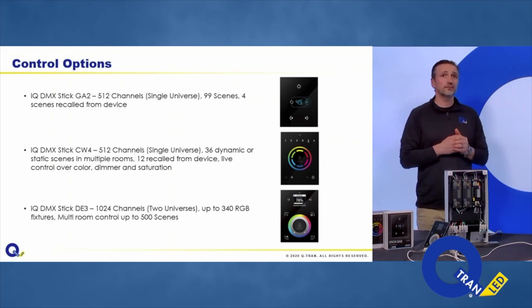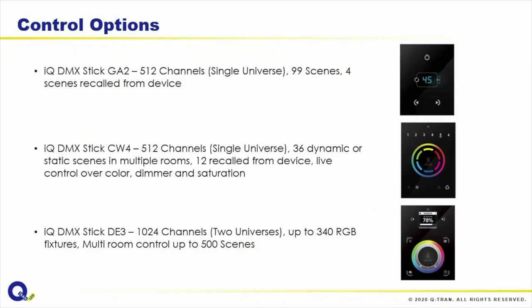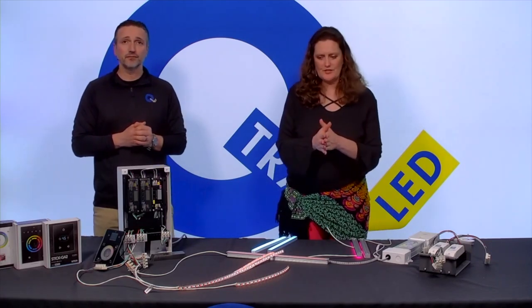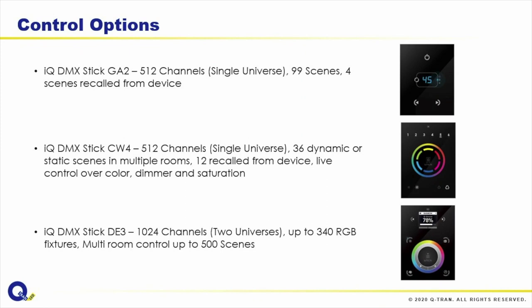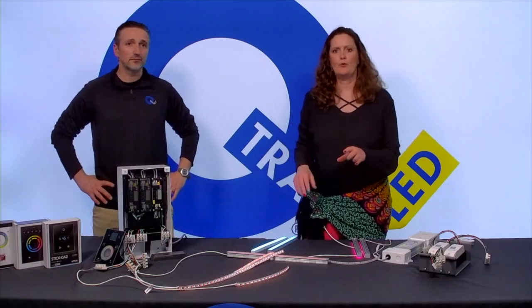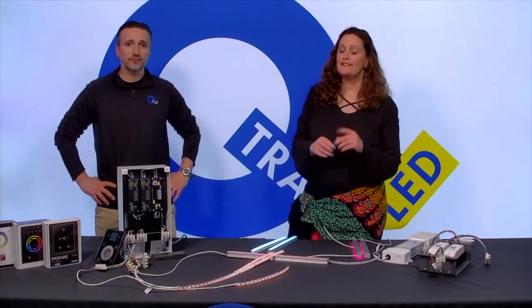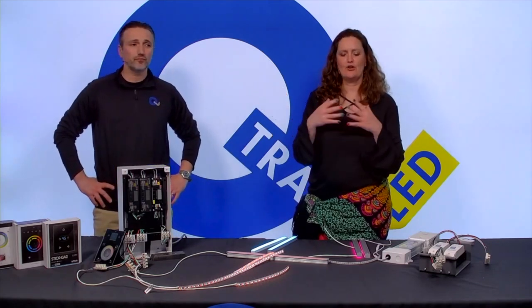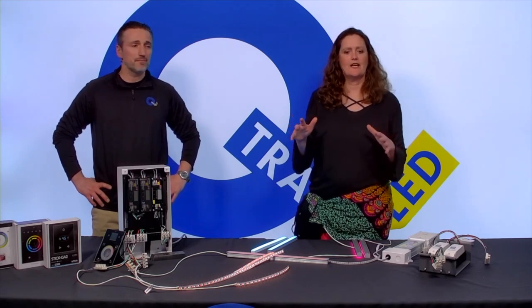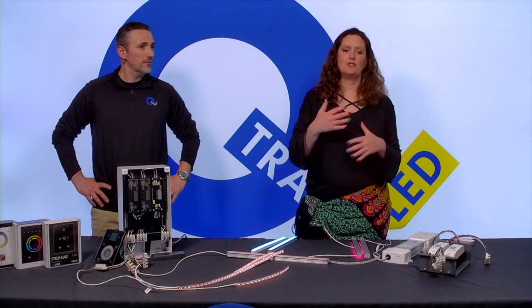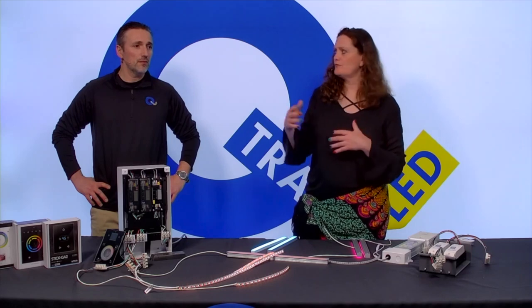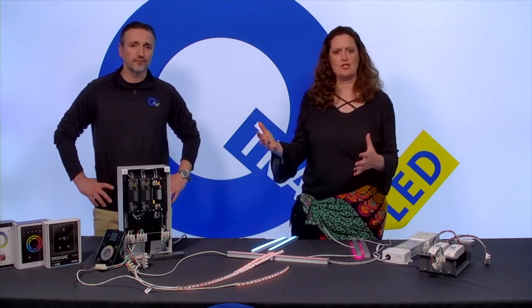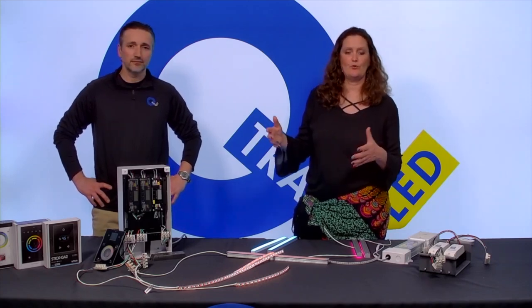To summarize the basic system: you have a DMX controller, a wire, and the system you're trying to operate. All three work together, with wiring being the most critical component. The DMX 512 wire between your control system and power supply is not a Q-Tran item — you must use DMX 512 standard wire. We are not a controls company. For commissioning, reach out to your local rep or an integrator. We provide advice and troubleshooting support.